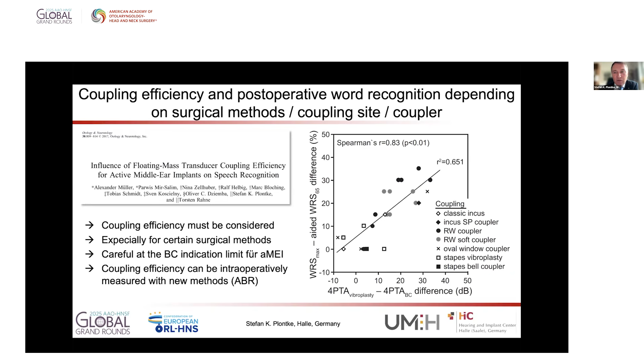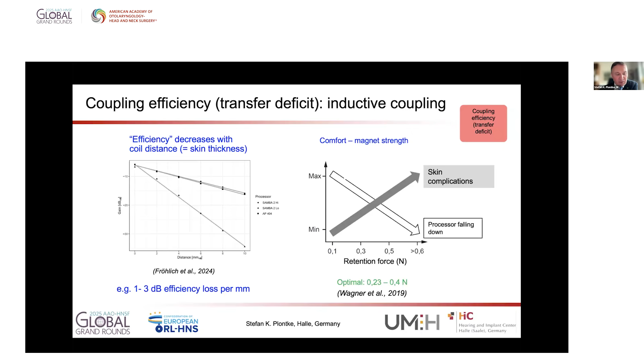Also, coupling efficiency plays a role in the speech processor. So the efficiency of coupling decreases with coil distance, meaning with the thickness, and this could be as much as 1 to 3 dB per millimeter efficiency loss. And again, this plays a role when we max out or when we go near the indication range of the devices. And then when we do surgery, we also have to consider that there is probably an optimal retention force of the magnet of 0.2 to 0.4 Newton, getting a good balance between skin complications and the processor falling down.